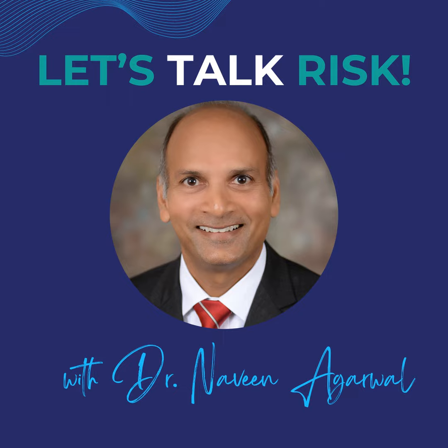Thanks for the time too, and kind of piggyback a little bit on what John talked about earlier. To do this stuff well, you have to start early, and you have to start often, and really understand, from the usability side, how the product is going to be used by the actual clinicians. That can really drive a lot of your thoughts from a design perspective and a risk perspective too, to understand what the potential hazardous situations and harms are.